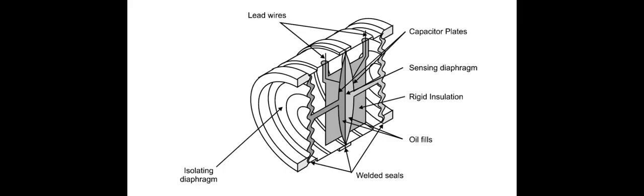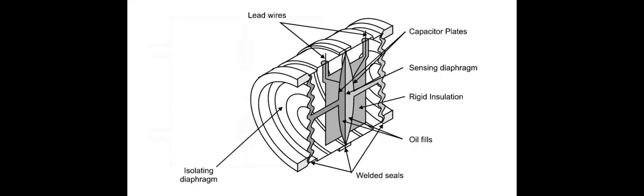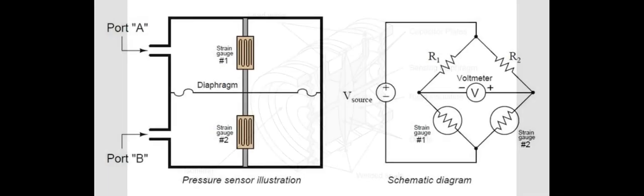Capacitance in this circuit is measured using an AC current, but through some electronics in the head of the controller, this is converted into a DC current which will give you an output in your range between 4 to 20 milliamps. Basically, the electrical output is directly proportional to the pressure that's put on the plate.